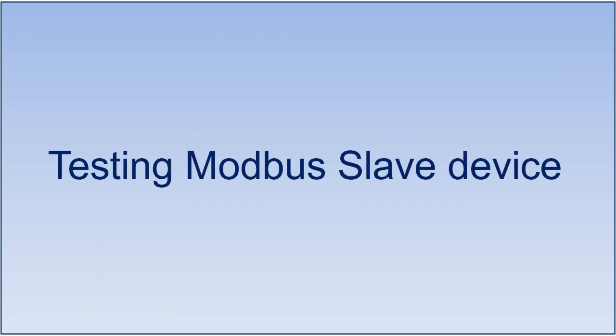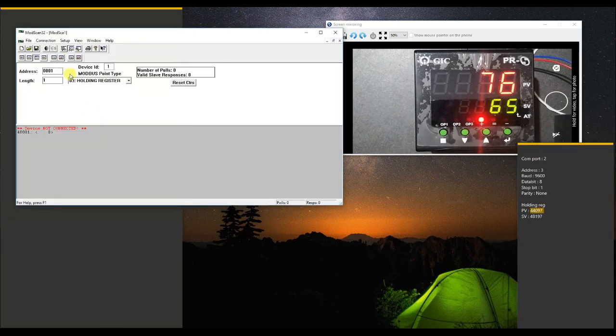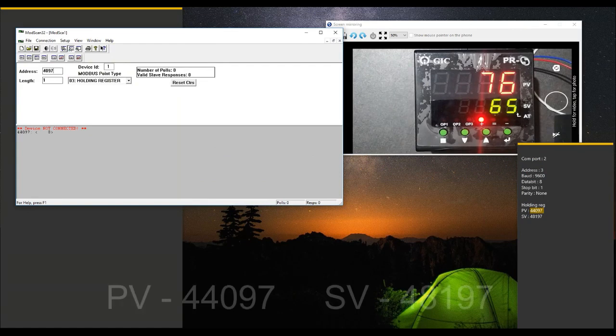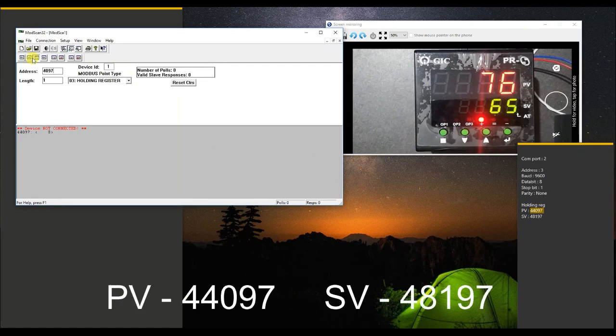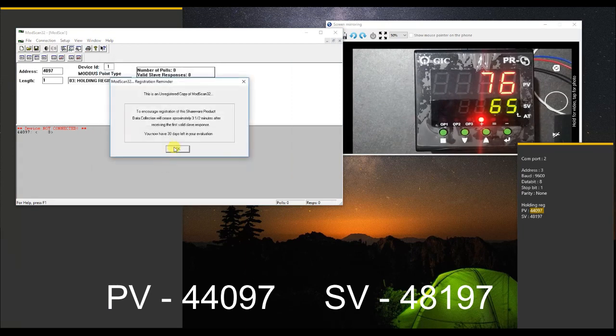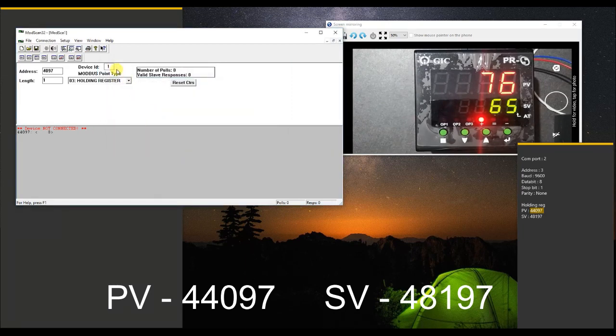Now let me first demonstrate the PID controller data on the Modbus register. I will read the PV value and then write the SV value from the Modscan software. Here PV is coming on the holding register 44097.